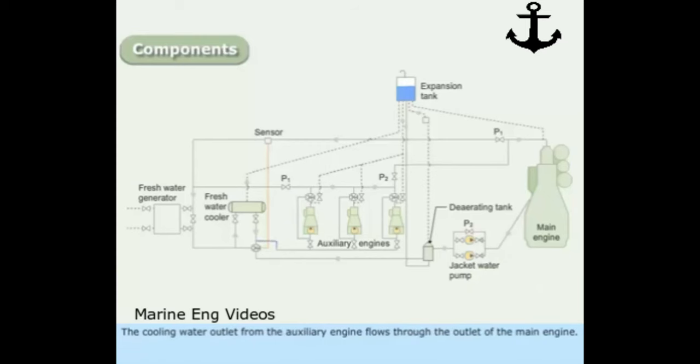The cooling water outlet from the auxiliary engine flows through the outlet of the main engine. The water circulates inside the main engine and flows back to the de-aerating tank through the pump bypass valve P2.